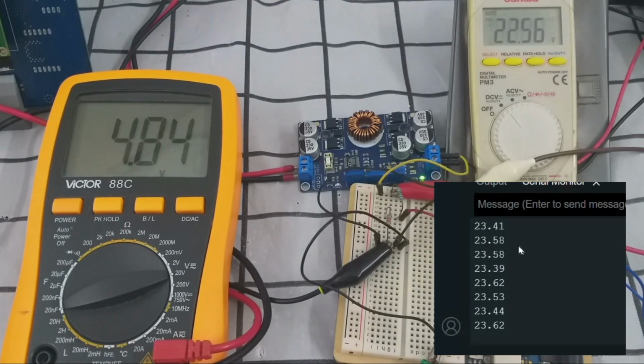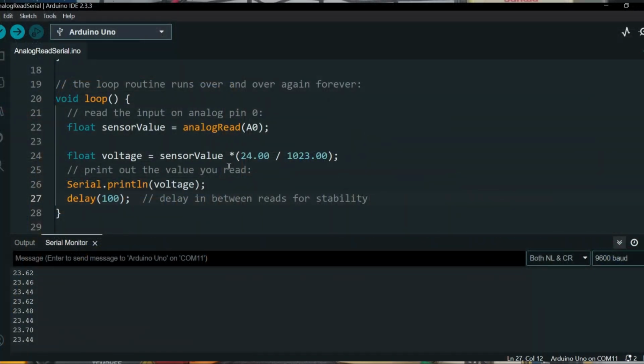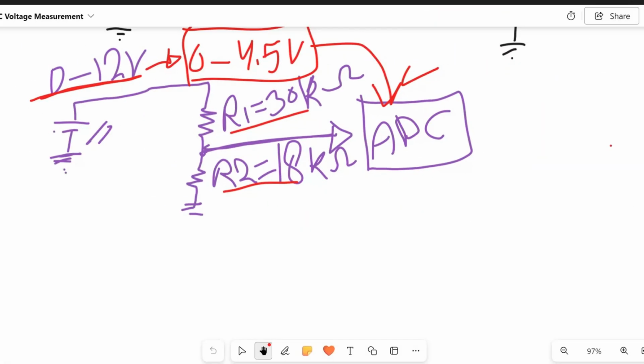Here we go. So now we're injecting 22.5 and the output is 23.6. So the offset is getting bigger now, which again we need to resolve by calibration, or two-point calibration to be exact. Okay guys, so this is the code for how we managed to read the 24 volt DC using a voltage divider. Well guys, so here we reached the end of the video.